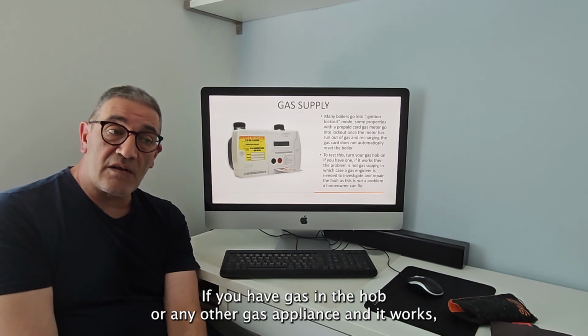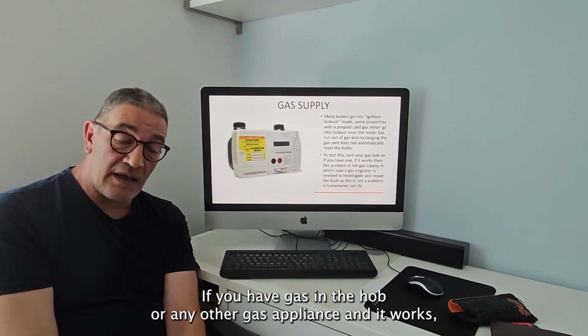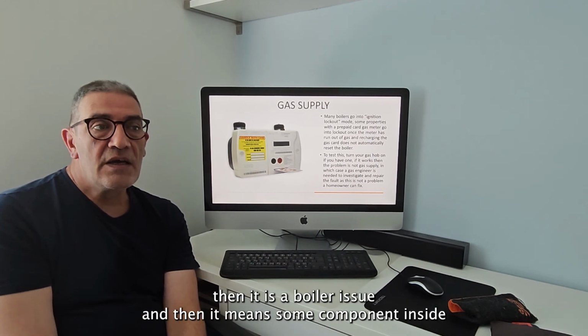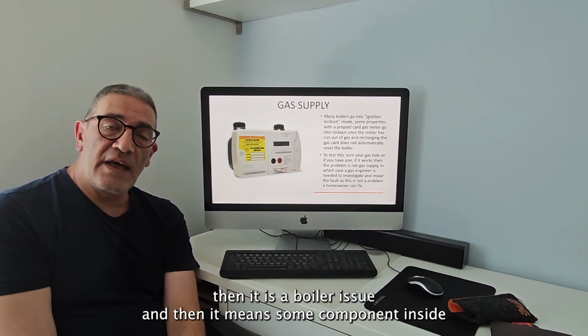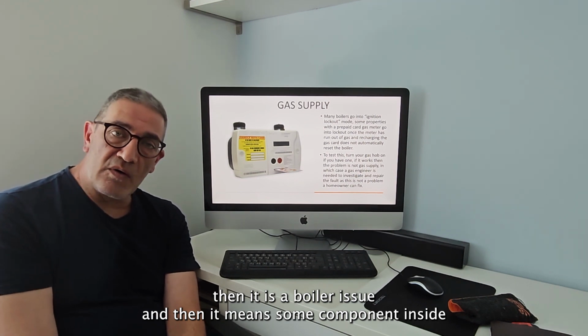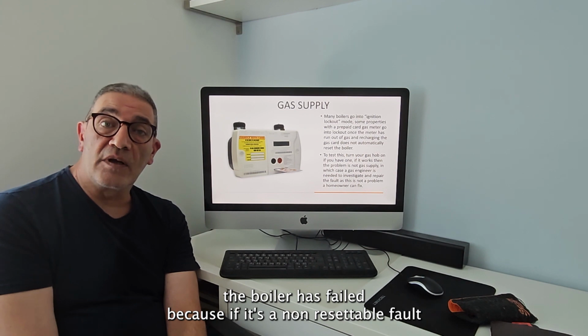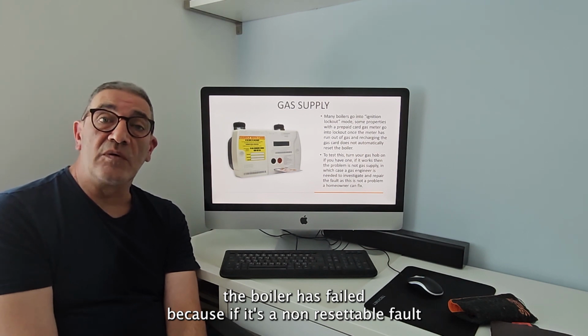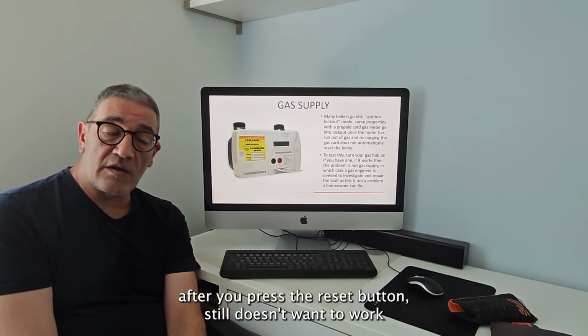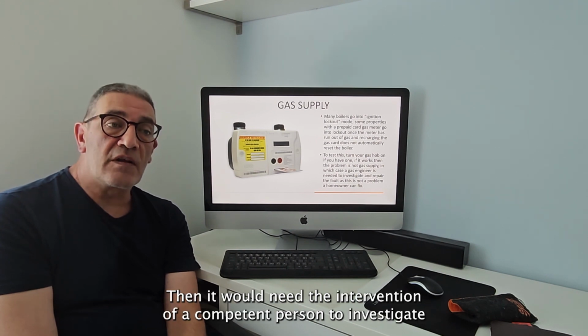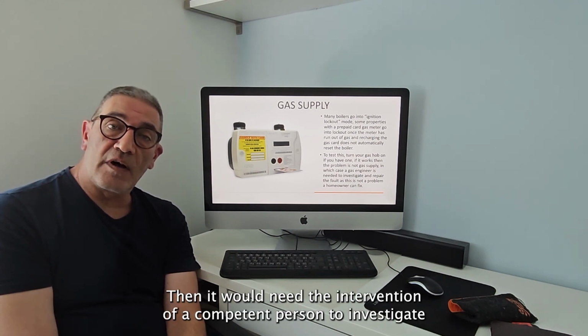If you have gas in the hob or any other gas appliance and it works, then it is a boiler issue, and it means some component inside the boiler has failed. Because if it's a non-resettable fault, and after you press the reset button it still doesn't want to work, then it would need the intervention of a competent person to investigate.